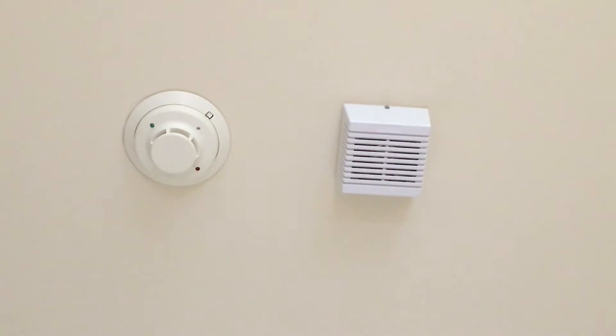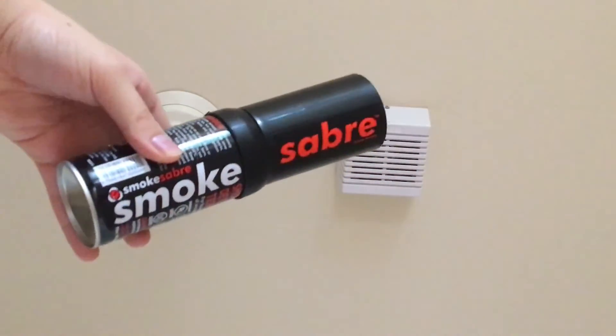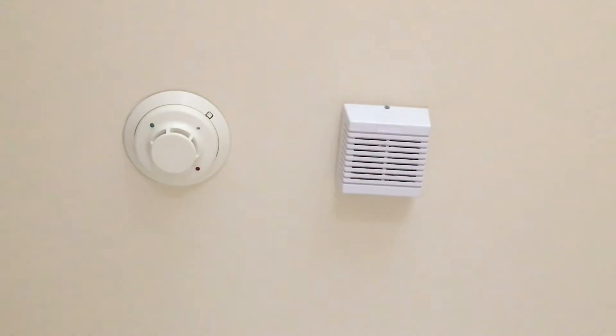Someone mentioned that the test button tests the chamber — that is not true. With the majority of smoke detectors, there is no smoke detector that uses the test button to actually test the smoke chamber. All it does is test the detector's ability to communicate a fire condition, not test the actual smoke detector chamber itself. In order to test the smoke chamber, we're going to be using this nice little can of Smoke Sabre, which I will be doing the flick as many of my viewers have requested.